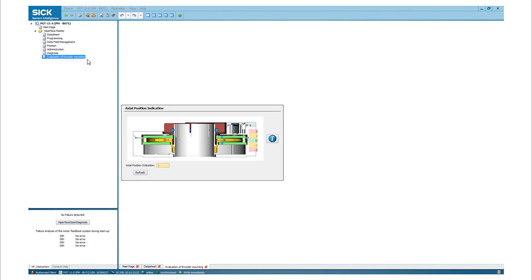If a SES-SEM-70 or SES-SEM-90 is connected, it is possible to check if it is correctly mounted. Values within the green and yellow marked range are acceptable. If the rotor position is in the red marked range, the sensor is not mounted correctly. Please check the mounting instructions.